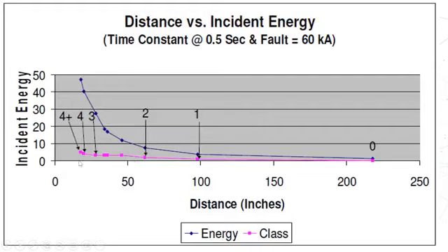At a particular location, if a person is working at 18 inches, the incident energy is 50 cal per centimeter square.